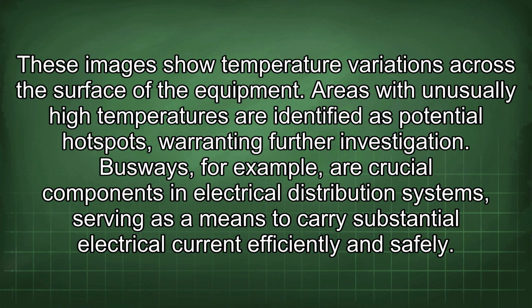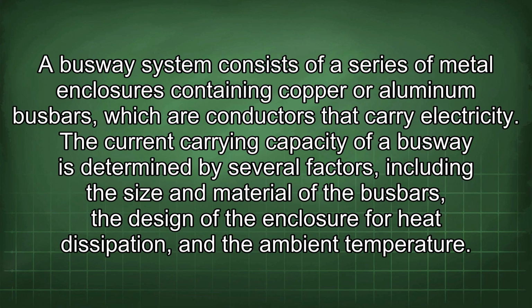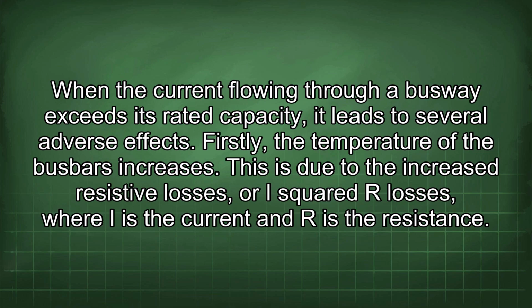Busways, for example, are crucial components in electrical distribution systems, serving as a means to carry substantial electrical current efficiently and safely. A busway system consists of a series of metal enclosures containing copper or aluminum busbars, which are conductors that carry electricity. The current carrying capacity of a busway is determined by several factors, including the size and material of the busbars, the design of the enclosure for heat dissipation, and the ambient temperature. When the current flowing through a busway exceeds its rated capacity, it leads to several adverse effects.